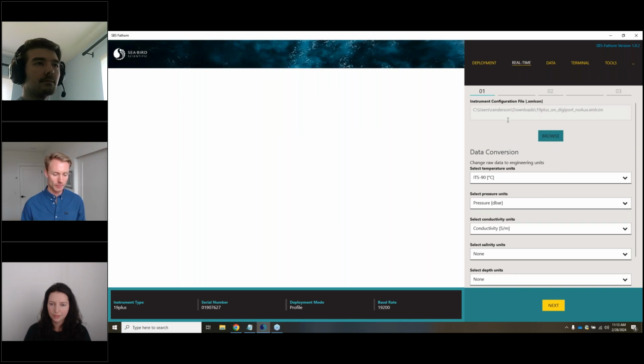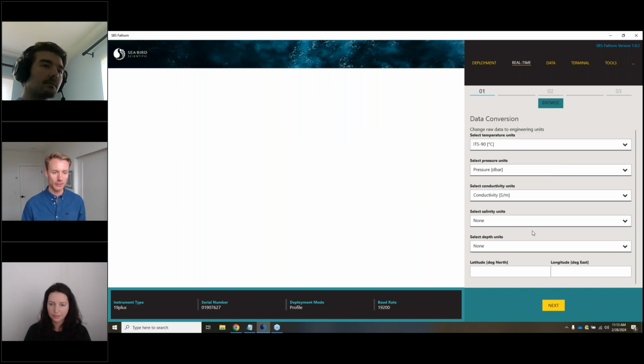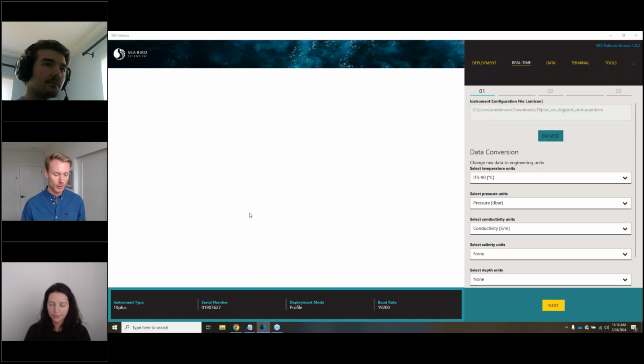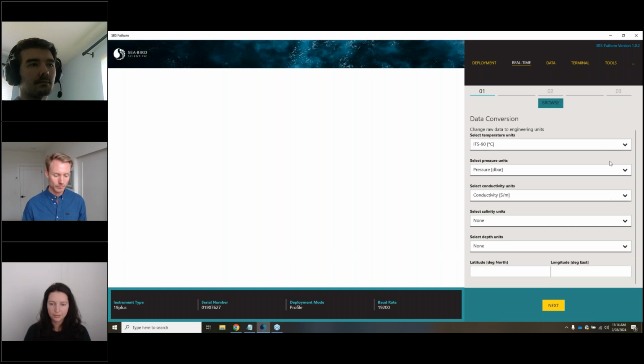Here, we can set up all the settings that we have to do for real-time data collection. I'm going to load in an XML con file. This contains, if you're not familiar, all the coefficients for the sensors that are on the instrument, specifically for the auxiliary sensors. So if you have a bunch of auxiliary sensors, all the coefficients need to come from that XML con file. In this case, we don't have any auxiliary sensors, so they didn't pop up, but you can see we have different drop downs for each parameter. So we can select the units that we want the temperature to be in, the pressure, and the conductivity.